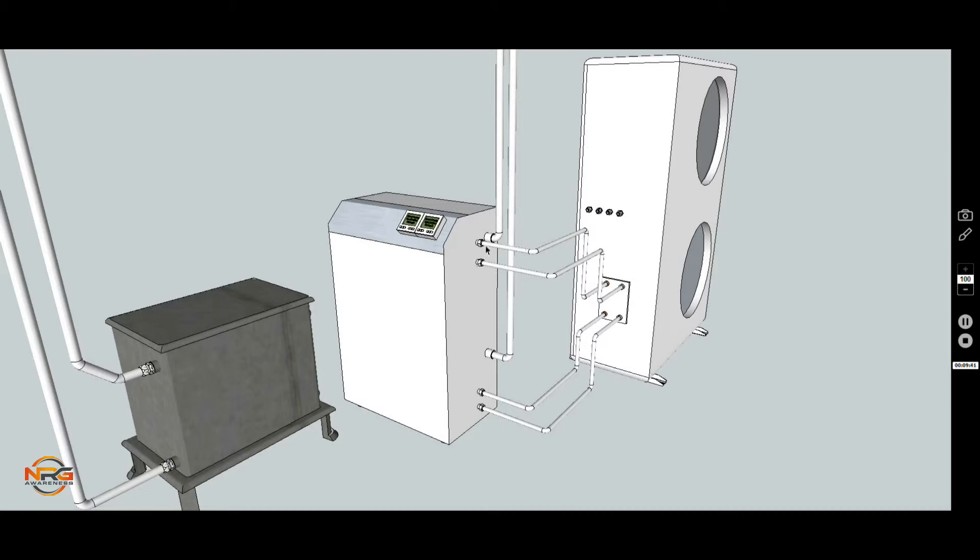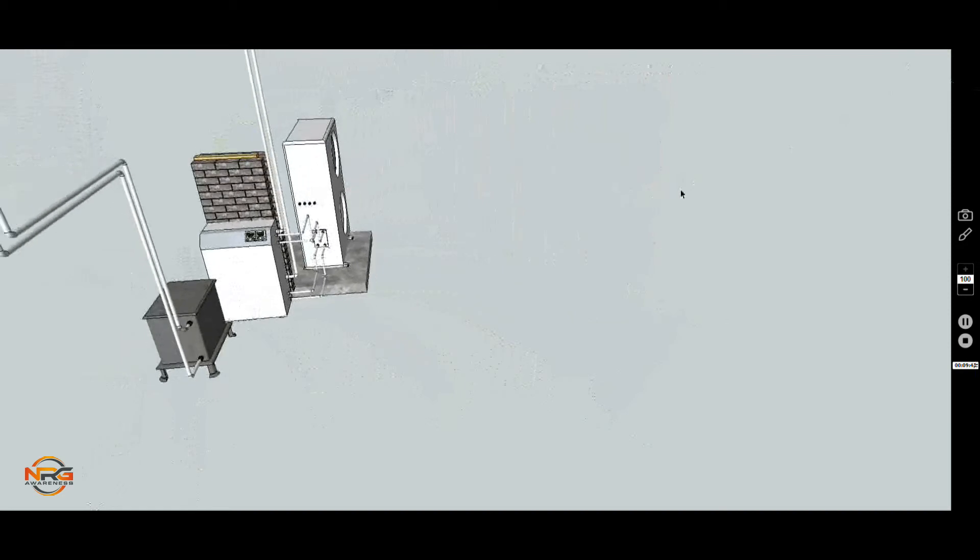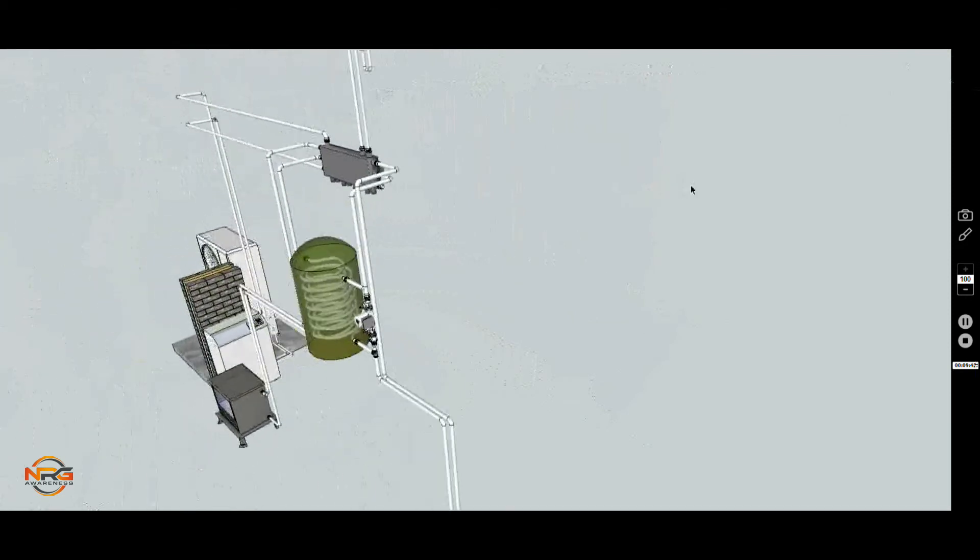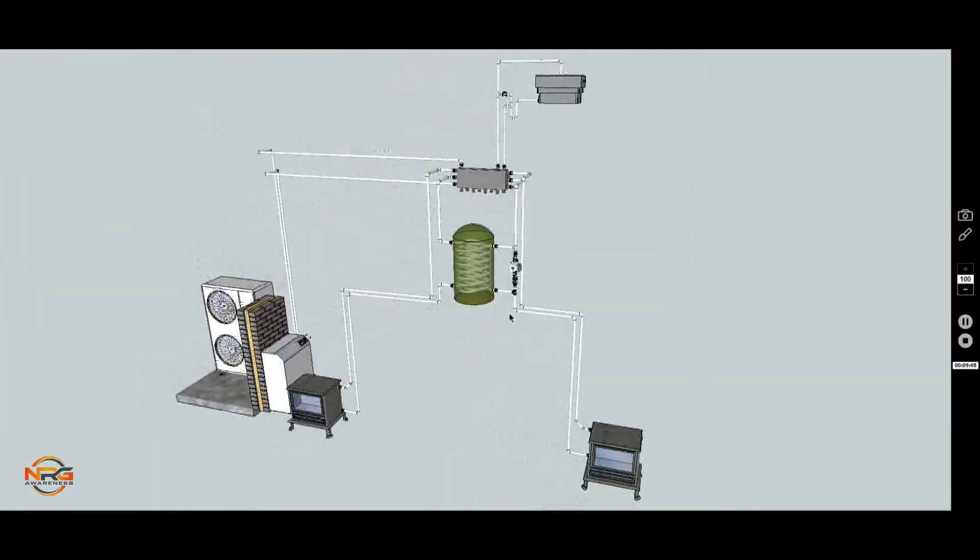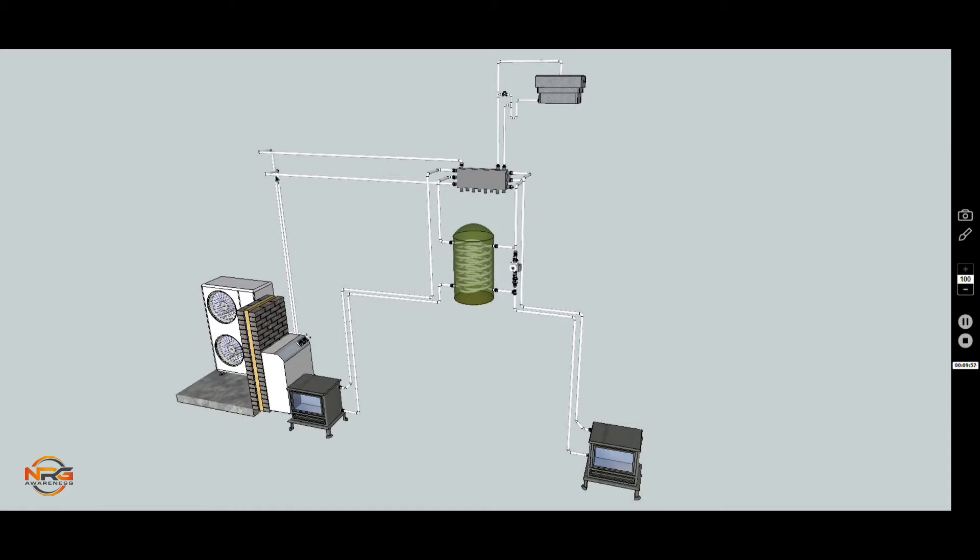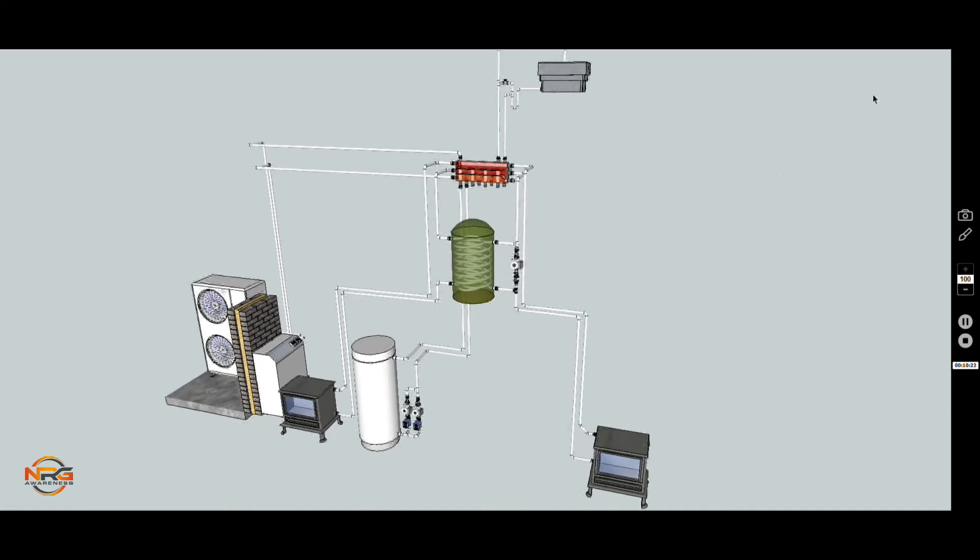We have a situation now where the solid fuel stoves can work on their own, or the heat pump can work, or they can all work together. As long as the return water temperature is below the temperature required limit set for the return of the heat pump, the heat pump can work away perfectly along with the solid fuel systems. So we see we have a perfectly safe primary circuit from the right hand stove to the manifold and upwards through the manifold, down through the coil and back, and likewise here up into the manifold, down through the coil and back. And we have the heat pump ready to deliver heat in, taking the coldest water coming back from any system return.